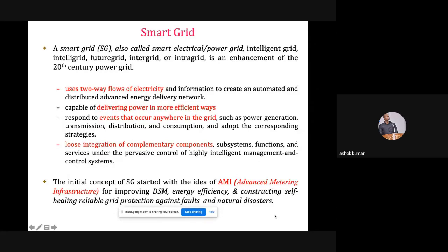Demand side management, in the sense of the meter—do you know the difference between contract demand and maximum demand? Let's say an industry has a contract demand of 10 kVA. That is the supply requirement the industry requested from the DISCOM, and they have supplied it. But that industry's maximum demand may be 8 kVA or less. So that industry should control its maximum demand.